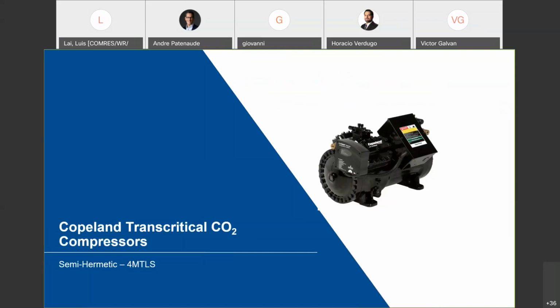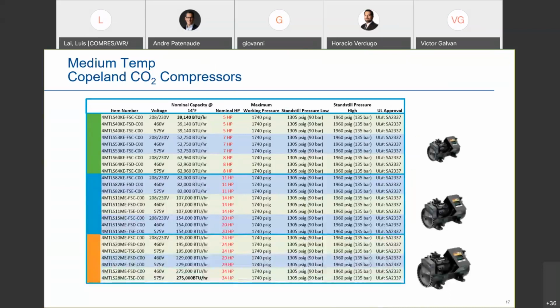So I wanted to start talking about transcritical compressors that we have to offer. The design was out of Europe and North Americanized. I say North Americanized because in Europe, if you see a lot of pictures online, you may see a plastic electrical box. And in Europe, they use a plastic and it's kind of rounded shaped electrical box. It's in the same position, but it's just plain plastic. In the US here, we need a metal box for UL. So that's why you may see a little bit of difference between one image or another.